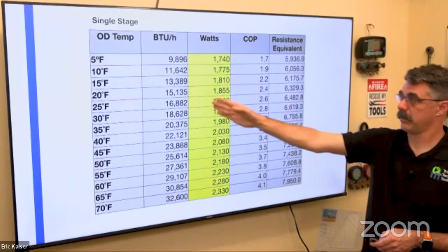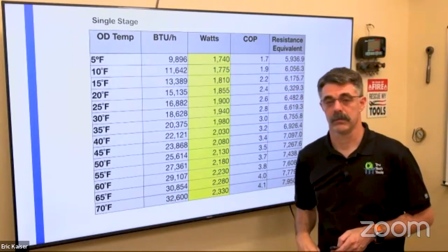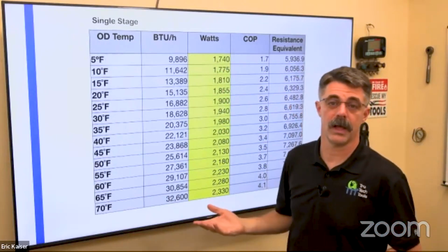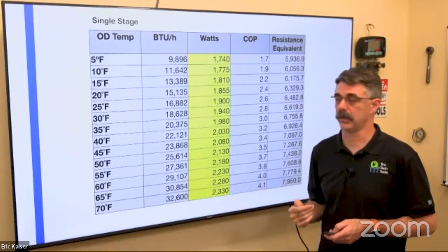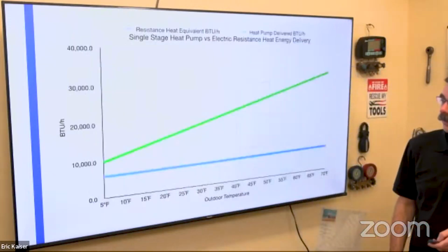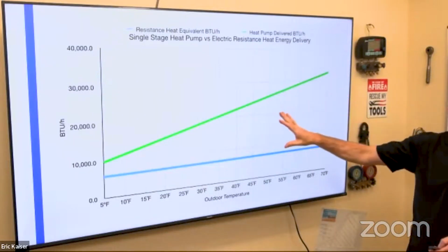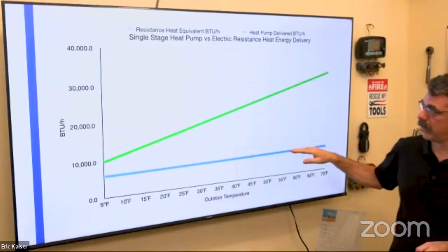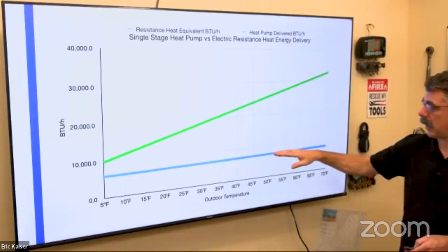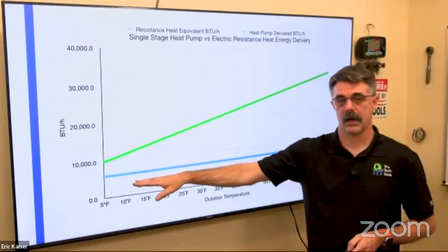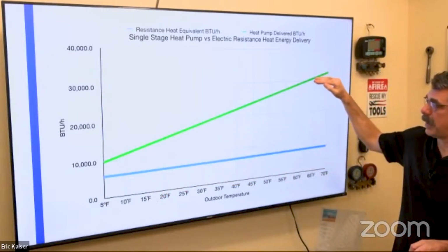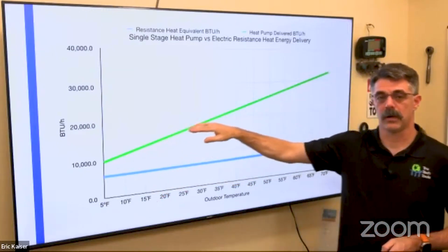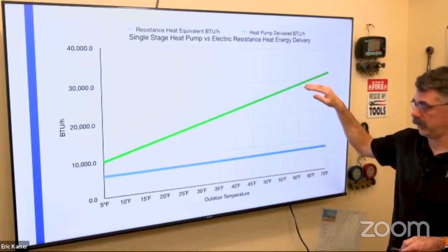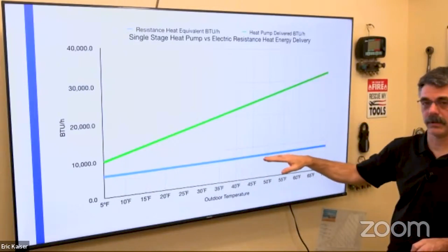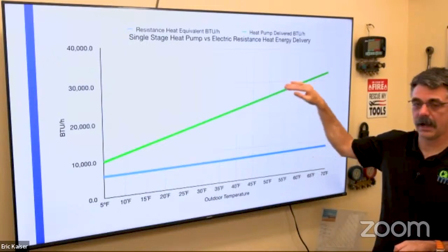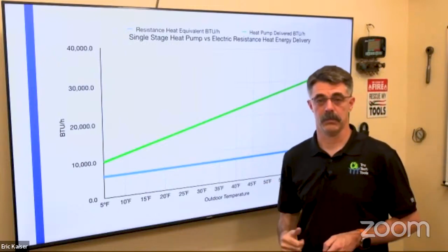Now, is the heat pump going to necessarily keep up with the house at that point? Who knows? I don't know until I have a load calculation and I develop something called a load slope. Right? And this is the first piece of that. Down here is plotted the equivalent resistance heat that I would be getting out of that unit, and this is my performance slope. This is how many BTUs I'm actually getting out. So this would be the same wattage into an electric heat. This is my actual BTUs out running the heat pump.